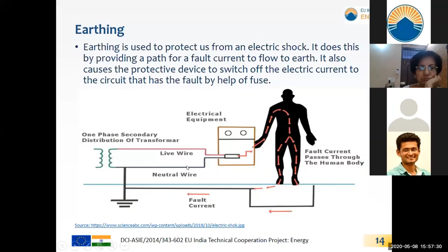Earthing in solar PV systems. Three separate earthings are required for a solar rooftop PV system. One is DC earthing, second is AC earthing, and third is earthing for the lightning arrestor. DC earthing is required for the solar panel, DC junction box or DC distribution box or DC array combiner box, and solar PV structures. AC earthing is required for the inverter and AC distribution box. And third, a separate earth pit is required for the lightning arrestor.